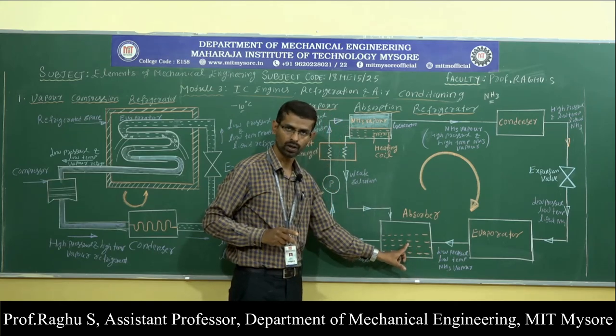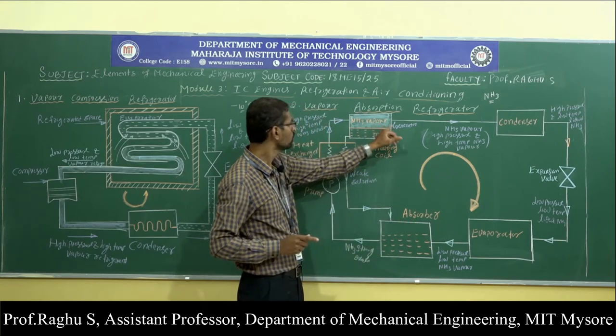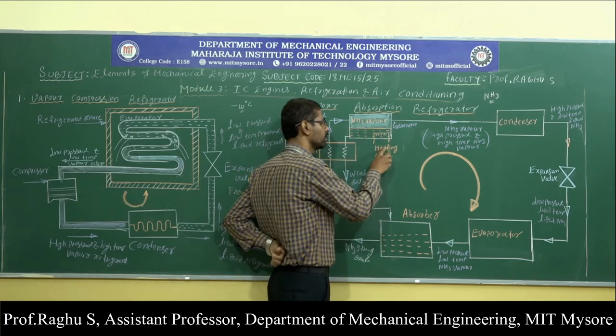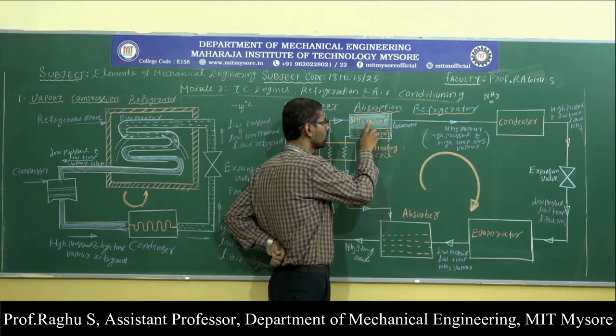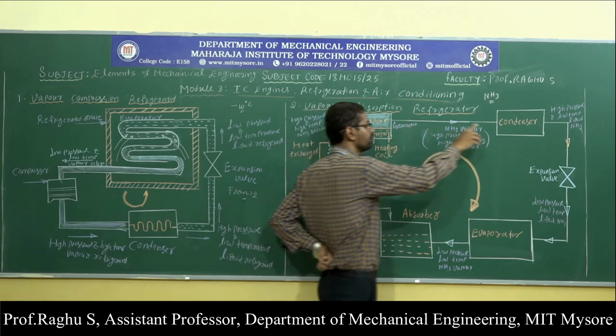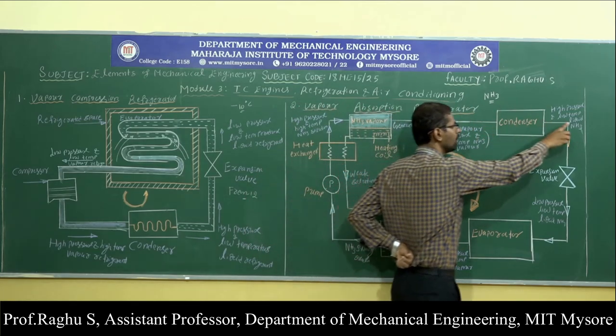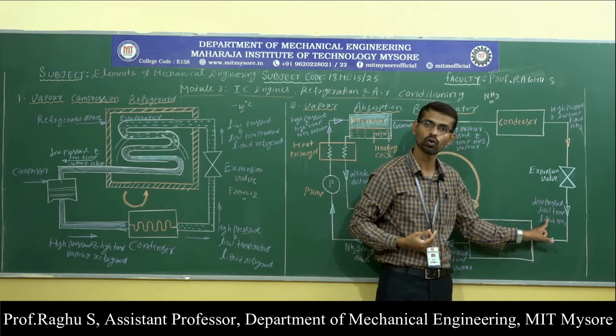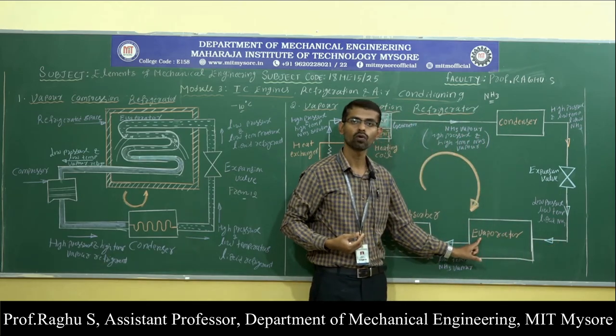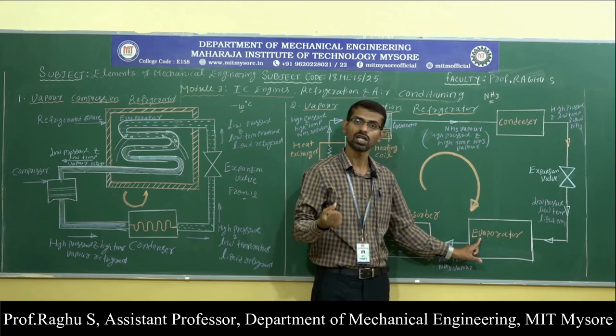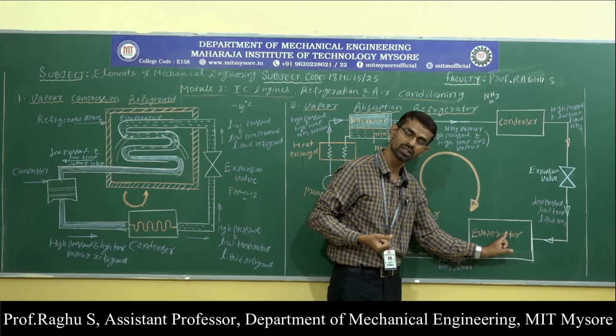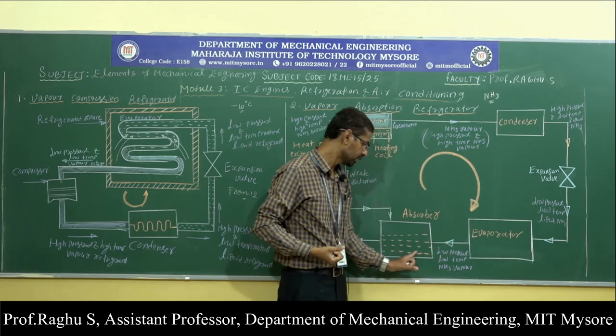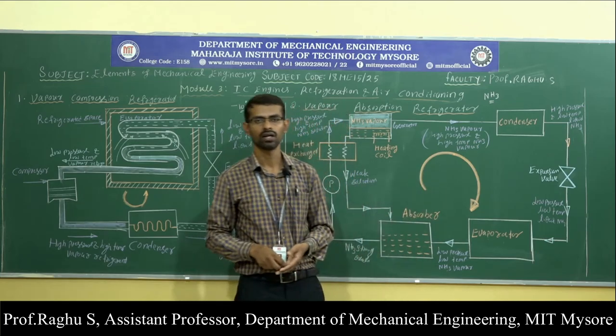Once the strong ammonia solution is heated in the vapour generator, ammonia vapour gets separated and the solution becomes weak. This weak ammonia solution is sent back to the absorber through the heat exchanger. In the absorber, ammonia vapour dissolves in the weak ammonia solution, forming strong ammonia solution again. This is pumped to the vapour generator, and the cycle repeats. The condenser converts vapour to liquid; the expansion valve reduces pressure and temperature; the evaporator absorbs heat from the refrigerated space, reducing its temperature; liquid ammonia converts back to vapour; the cycle repeats. This is the working of the vapour absorption refrigerator.